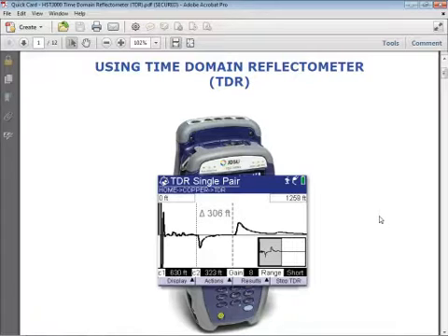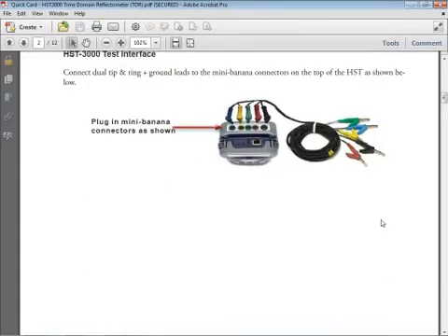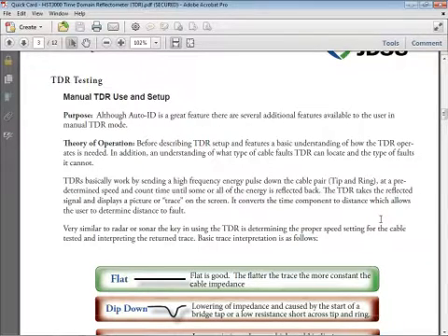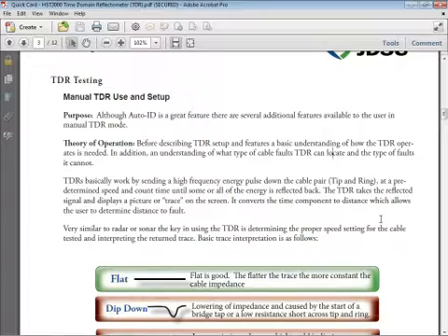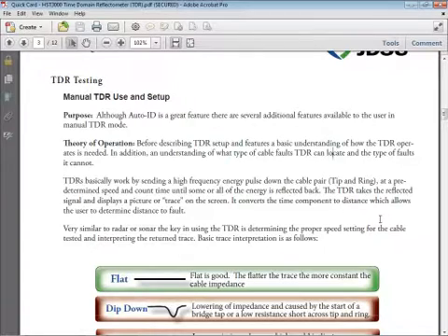What you're looking at here is a handout document provided by JDSU, so it's sort of a nice reference guide. TDR stands for Time Domain Reflectometer. It's kind of a fancy word for radar or sonar. TDRs are pretty basic instruments as far as theory of operation is concerned. They do one thing incredibly well, in my opinion, and that is count time. They have a supercharged clock, a very accurate clock built into them. They basically work by sending out a pulse of high frequency energy traveling down the cable pair at a known speed, because you, the operator, tell the TDR how fast it's traveling.